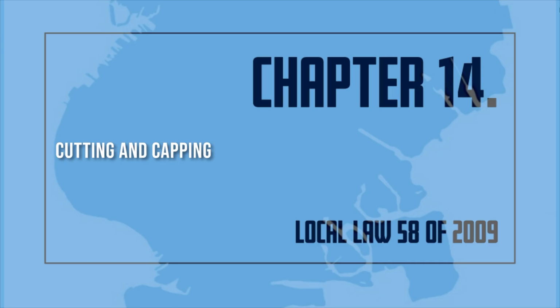Authorized licensees. Only licensed master plumbers or licensed master fire suppression piping contractors may cut and cap standpipes or sprinklers during demolition. The local law incorporates Technical Policy and Procedure Notice 3 of 2007, which became codified in Local Law 58 of 2009. For demolitions and gut rehabilitations, a registered design professional must have a variance to remove damaged or inoperable sprinklers. This filing must include a damage report and an explanation why the system can't be restored. The design professional must first file the variance with the Fire Department and have FDNY approval before filing it with the Buildings Department.